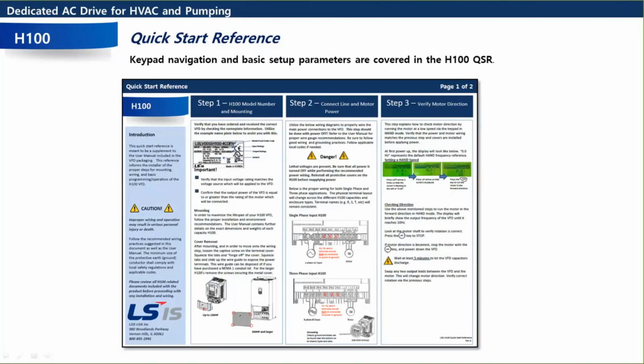But these quick start references, if you haven't used them yet, they're just short, kind of 2-page flyers almost, that just tell you the basics of how to wire up the drive, how to navigate the keypad, and then how to do basic parameters like motor data. How do you start the drive? How do you stop it? How do you control the speed? And maybe some safety functions in there or protection stuff as well. We recommend always starting out with following the quick start reference, and then you could add on the functions we're going to start talking about next afterwards. Kind of build it up and make the drive a little bit smarter and tailor it to your application.